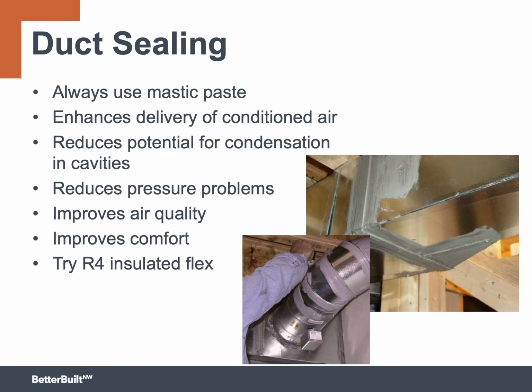Even though they're in the conditioned space, ducts still need to be sealed. We still want the air to get where it's supposed to go and not leak out somewhere along the way. It's not as catastrophic as it would have been in a conventional system, but it's still best for the air to go where it needs to go. Sealing ducts also reduces the potential for condensation in building cavities because the warm air is going to carry a lot of moisture with it. Air leaking from ducts could come into contact with some cold surfaces and cause condensation and the problems that come with it. Air quality can be improved because you're not blowing dust out from inside a pressurized building cavity.